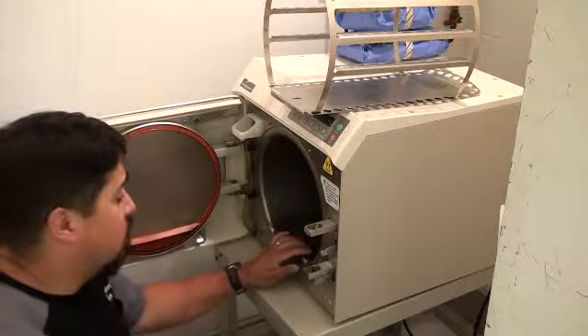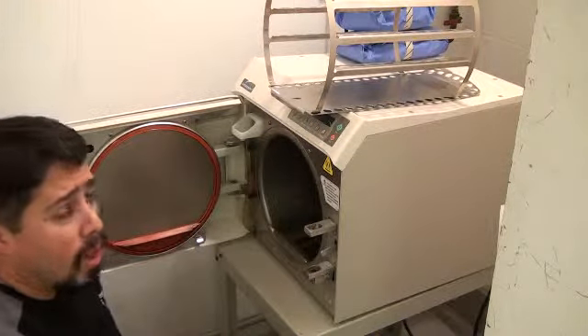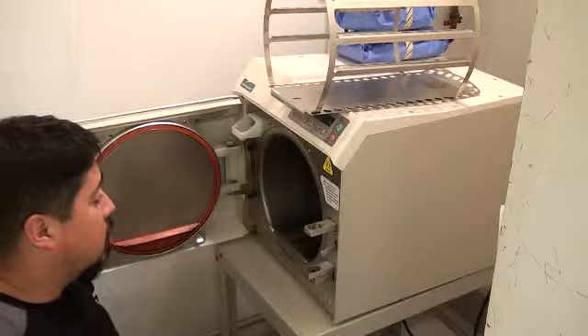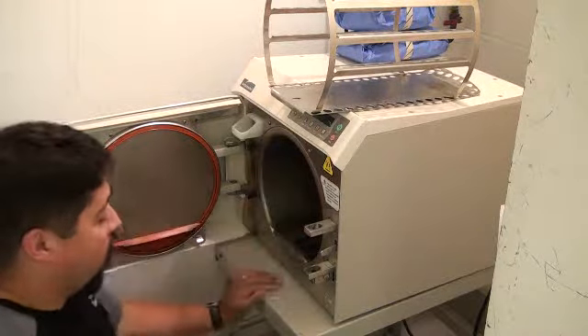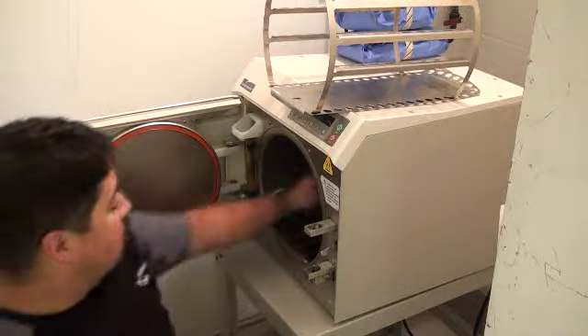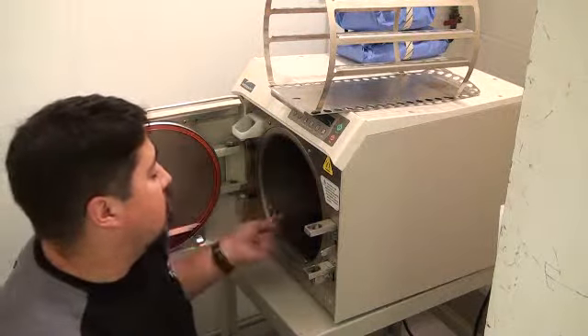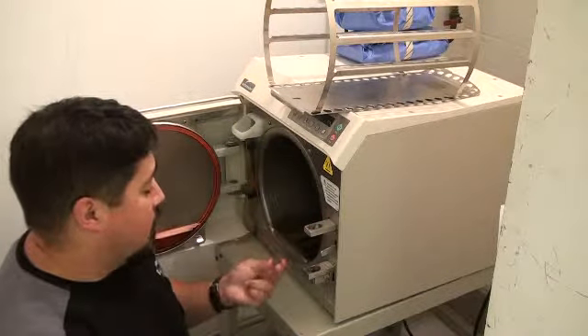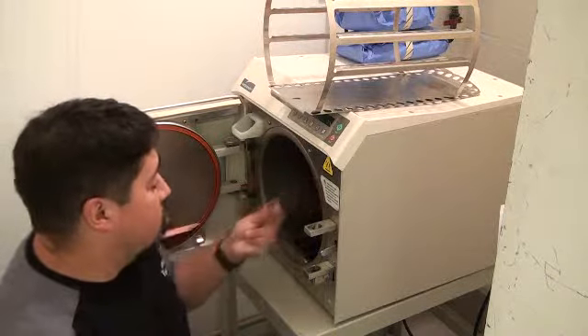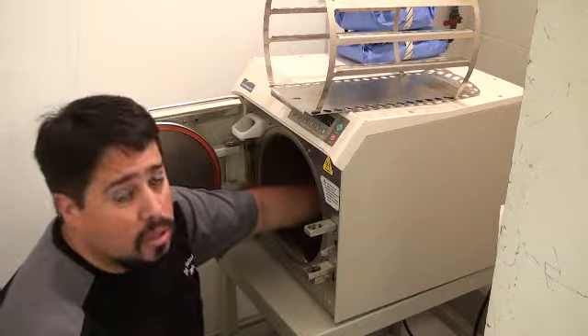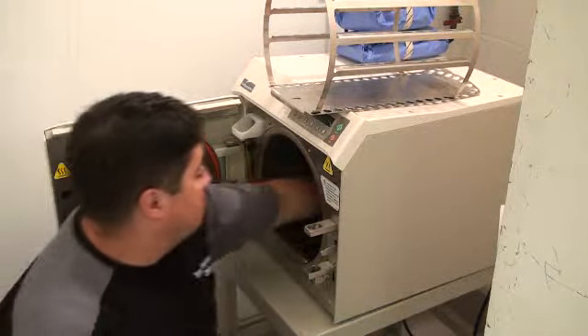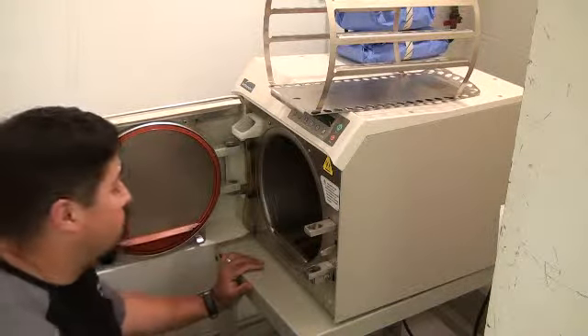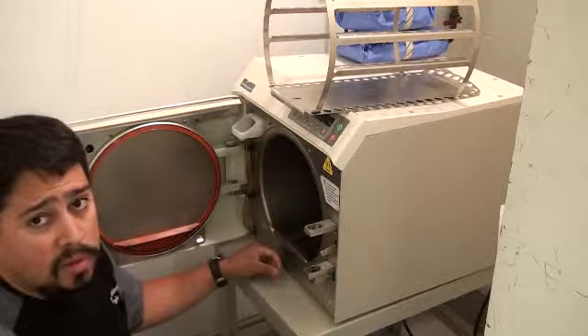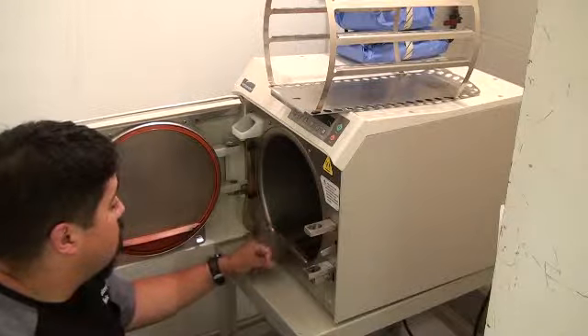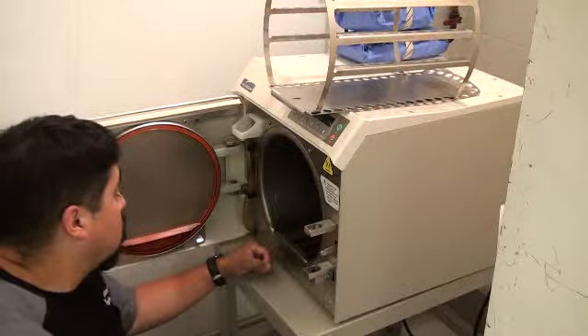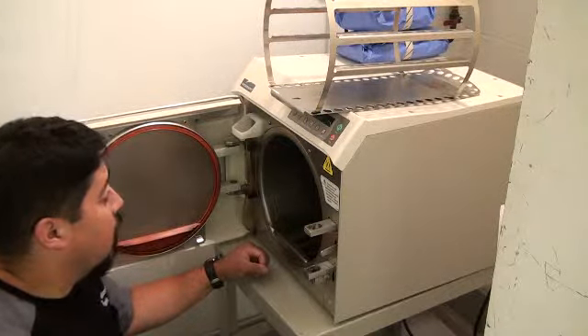On weekly cycles, this unit will actually give you a reminder that a week has passed and that it needs to be cleaned to do its weekly maintenance. All surfaces inside are wiped down with some Speed Clean and distilled water. There are vents inside for the steam, for the air to pass through, and for the water to pass through. They come with little wire mesh filters. Those will be cleaned with a soft brush to ensure that there are no particles in the little mesh material. There's one in the bottom and one against the back wall. There are copper coils in the bottom, which is the heating element that heats up the water. As long as everything is clean, this should keep the autoclave in good working order.